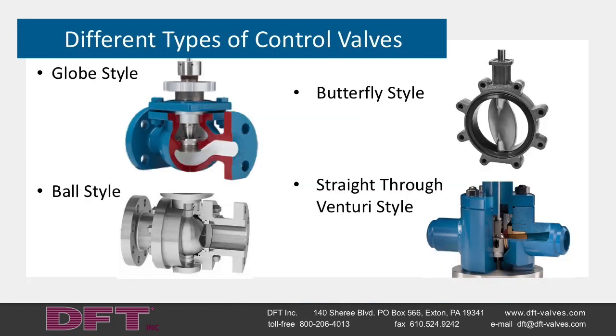There are different types of control valves that you may want to select depending on your CV requirements, your pressure recovery requirements, your modulating control requirements, and what kind of shutoff you require. Globe-style control valves are used in applications that require low CV, low pressure recovery, fine modulating control, and a range of shutoffs. Ball-style control valves are used in applications that require high CV, high pressure recovery, coarse modulating control, and tight shutoffs.